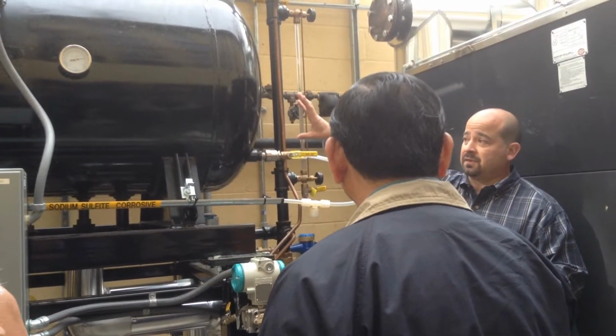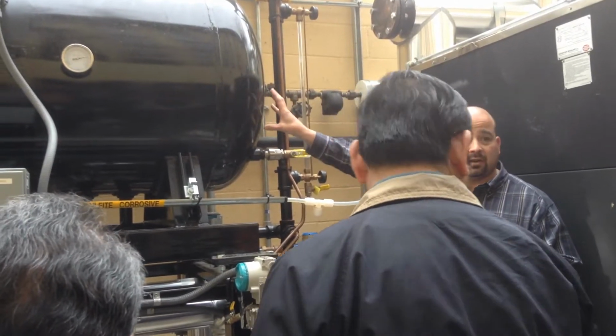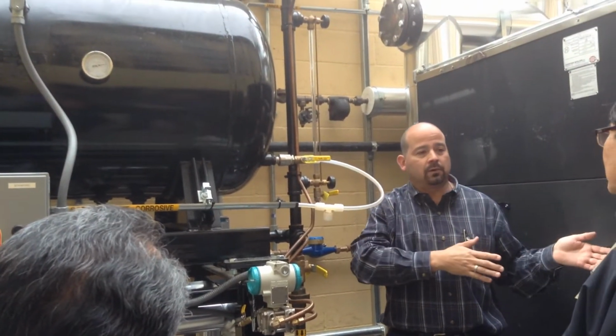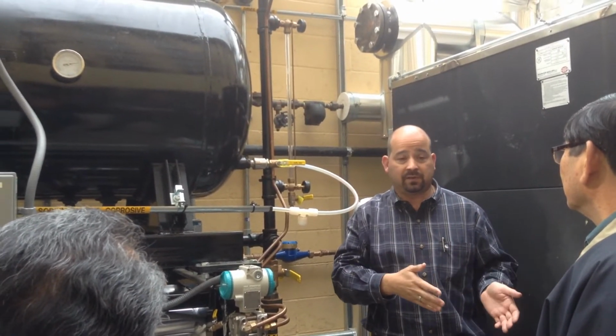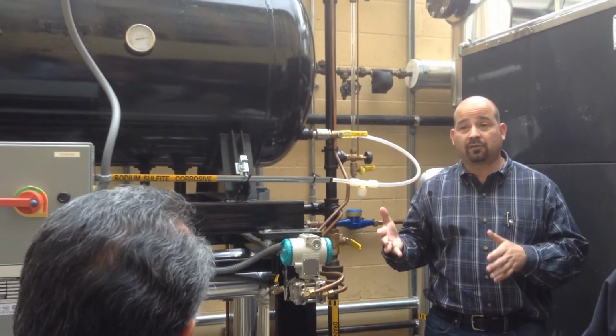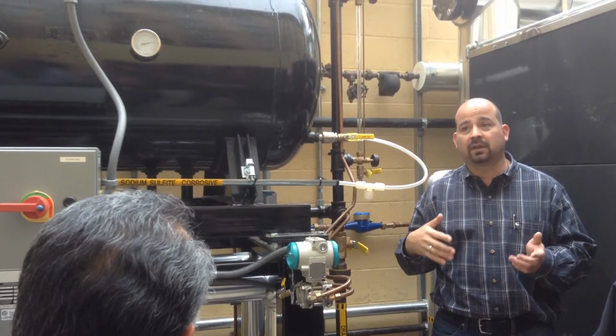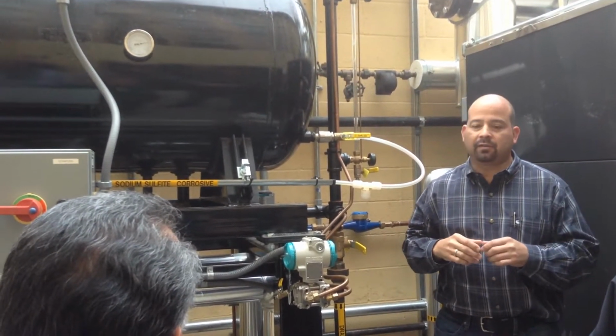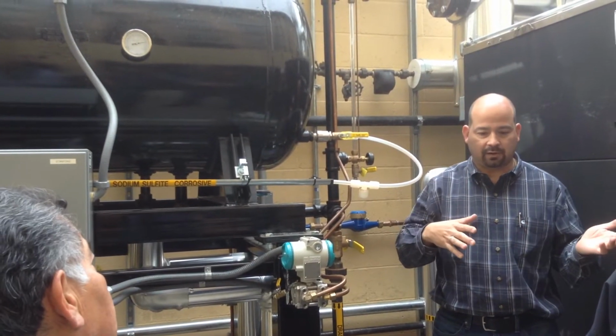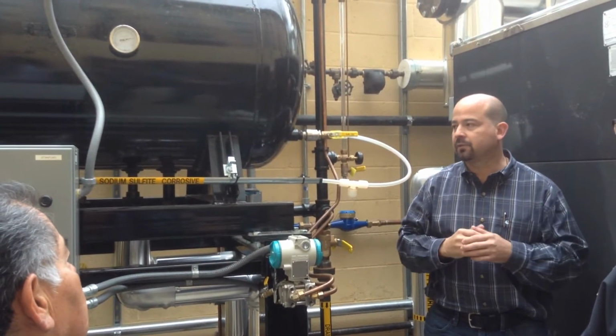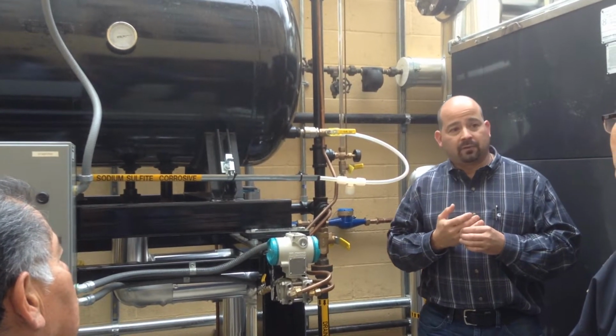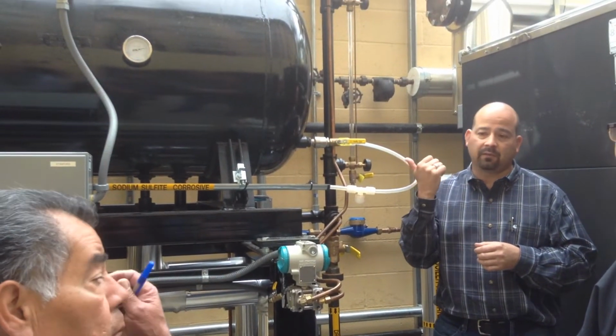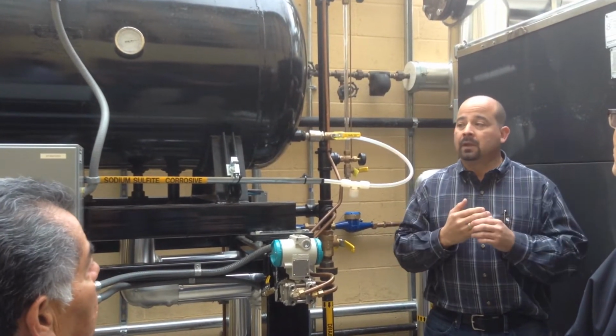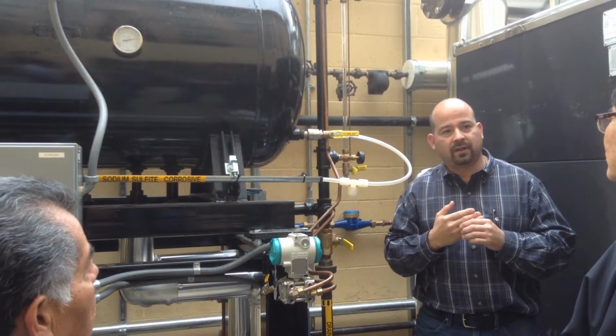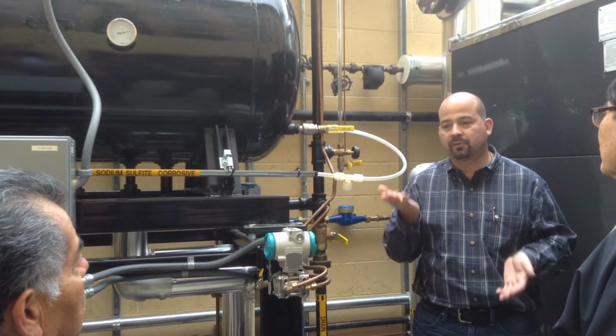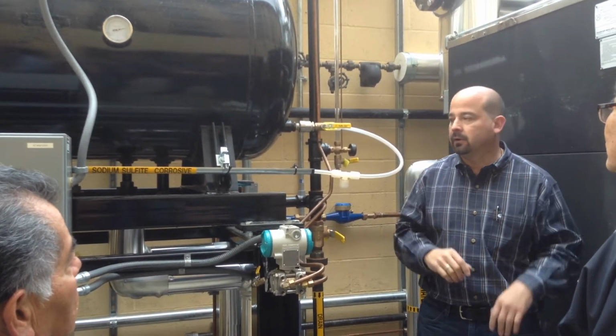What I like to do too is discuss briefly the purpose of a deaerator. Every steam boiler needs to have a boiler feed system. The boiler feed system could be open to atmosphere, or it can be pressurized. When it's pressurized, it's considered a deaerator. The advantage to having a deaerator versus a non-pressurized, open to atmosphere tank is you can run at a higher temperature. The higher the temperature of the water in this tank, because it's under pressure, the less oxygen you have. That can damage the boiler. So higher temperature, less oxygen, hence the deaerator.